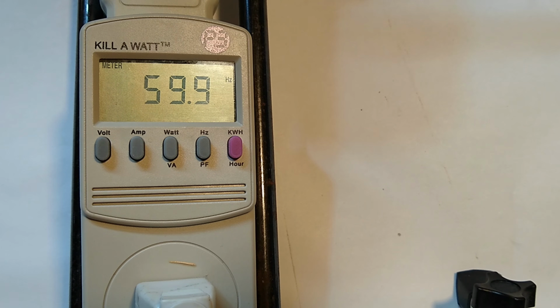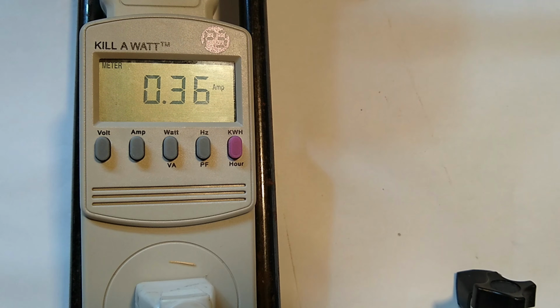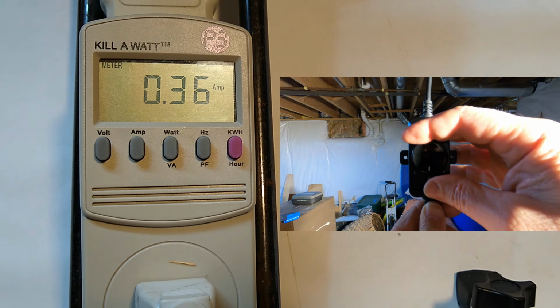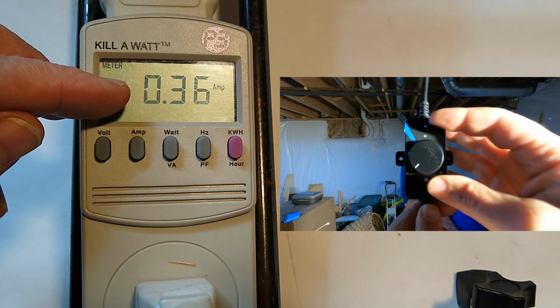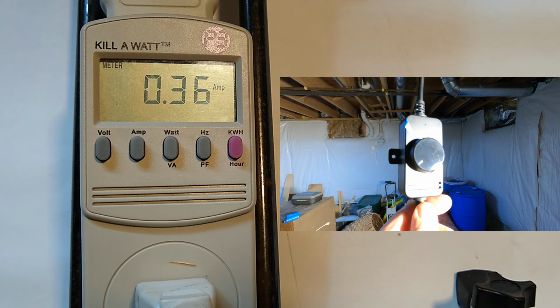I actually took readings at 25%, 50%, 75%, and 100% speeds. But I don't need all those numbers to accomplish my goal here. So I'll show the first measurement, then jump to the high speed measurement, which is all I really need. The duct boost controller is currently set at its lowest speed down by the L. And the current draw on low speed is 0.36 amps, also known as 360 milliamps.